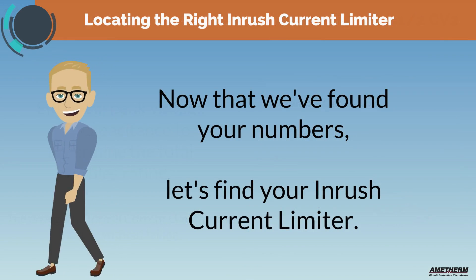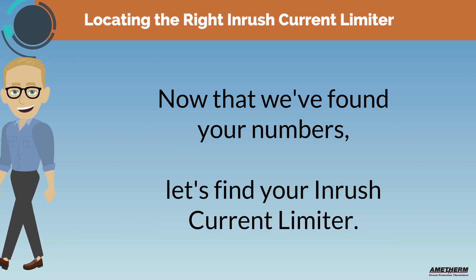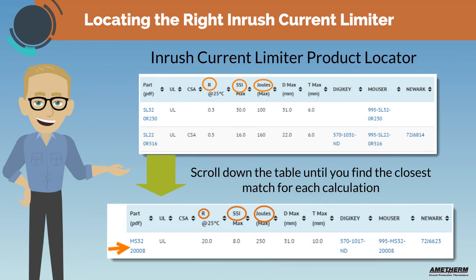Now that we've found the numbers, let's go find the inrush current limiter to match. You'll find our full line of inrush current limiters on our website as shown here. Simply click on the full line of inrush current limiters tab to display the component locator. Scroll down the table until you find a part that best matches your requirements for resistance, steady state current, and joules. Never select a part with numbers less than your results.